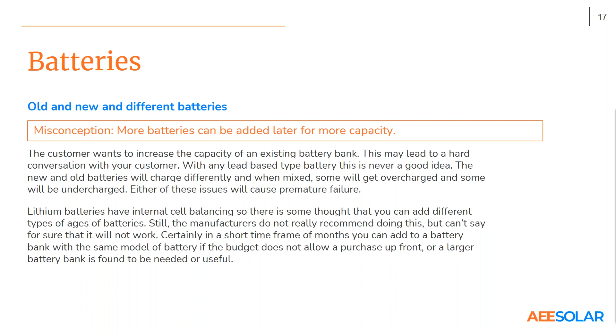Lithium batteries are a little different. The manufacturers do not recommend that you mix and match. Certainly you wouldn't want to mix different kinds of batteries because your communications aren't going to match, and that would be a problem for sure. And even different sizes of the same model, even if they communicate with each other, it's not recommended.